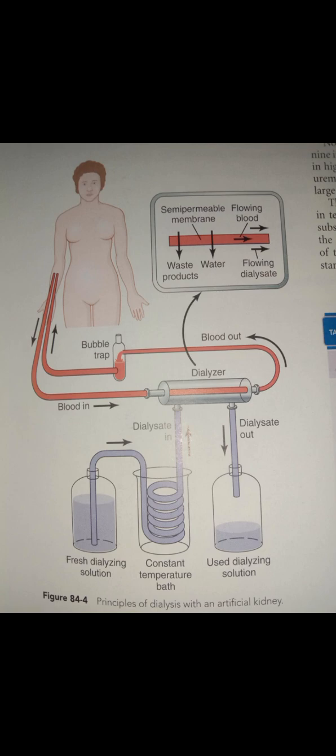Thus, the maximum rate of solute transfer occurs initially, when the concentration gradient is greatest as dialysis begins, and slows down as the concentration gradient is dissipated. In a flowing system, as in the case of hemodialysis, in which blood and dialysate fluid flow through the artificial kidney, the dissipation of the concentration gradient can be reduced and the diffusion of solute across the membrane may be optimized by increasing the flow rate of blood, dialyzing fluid, or both.